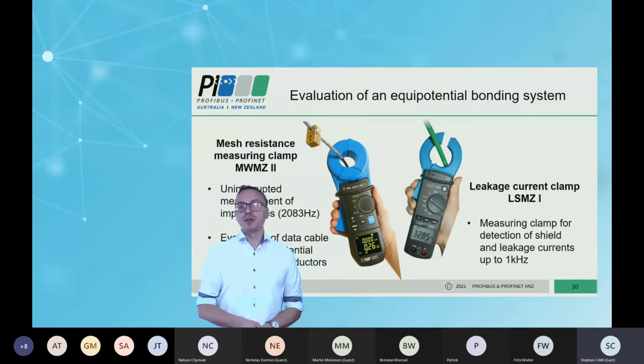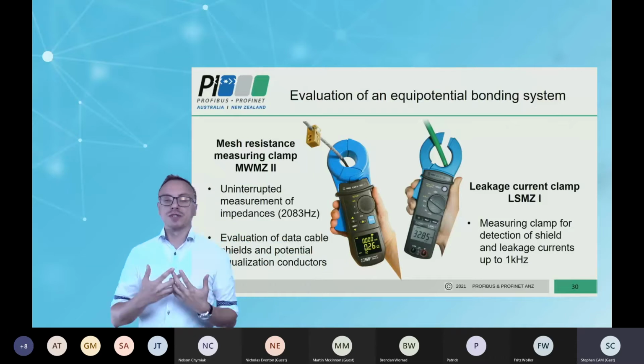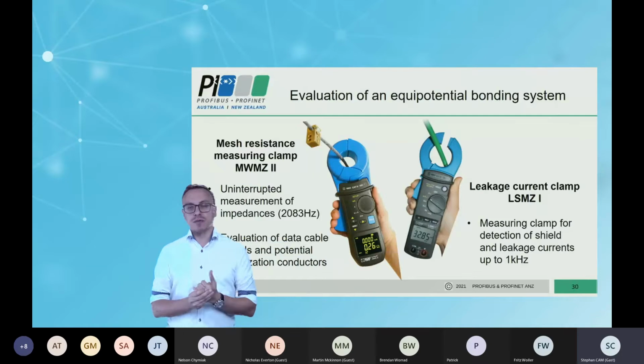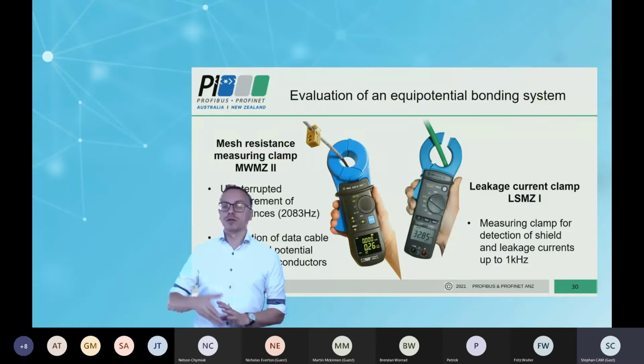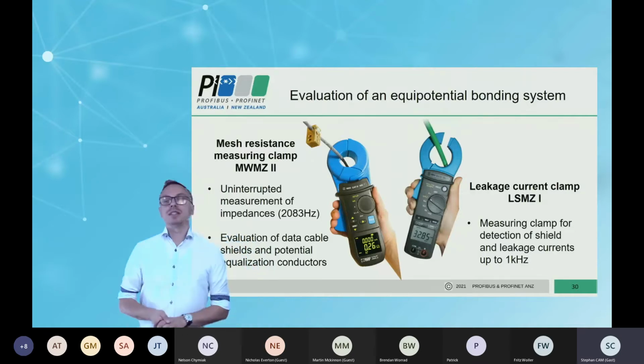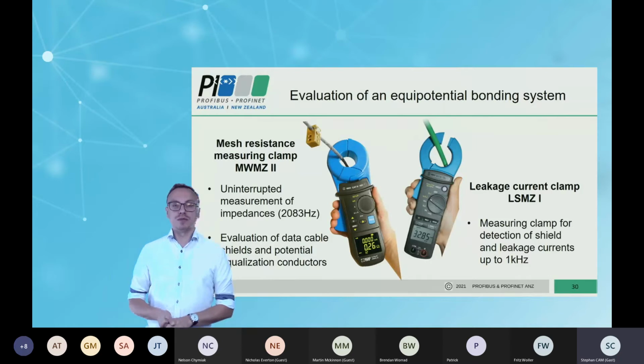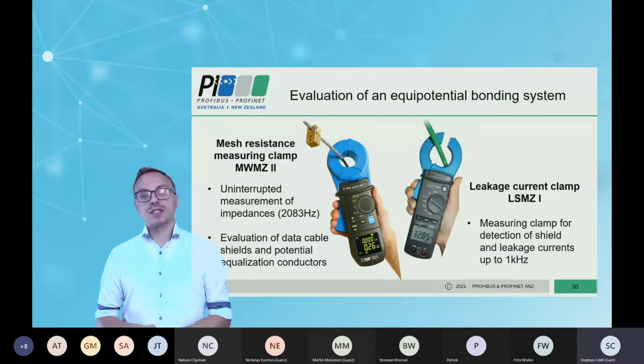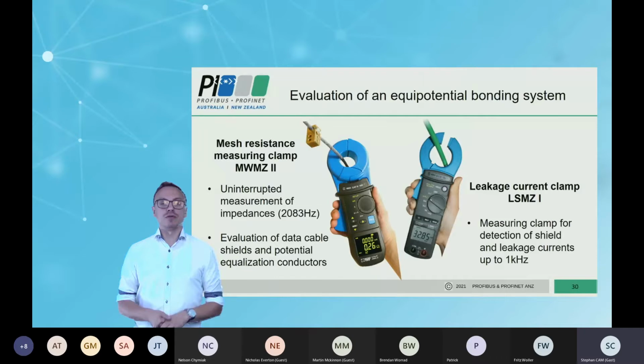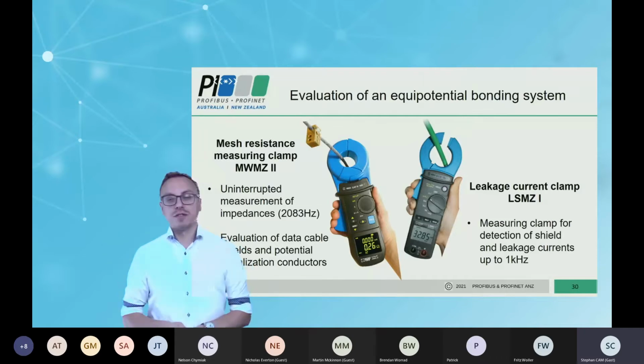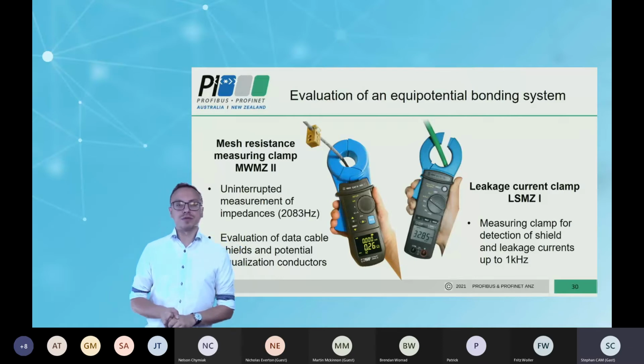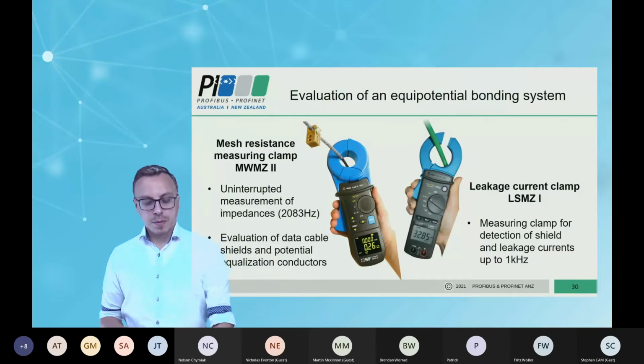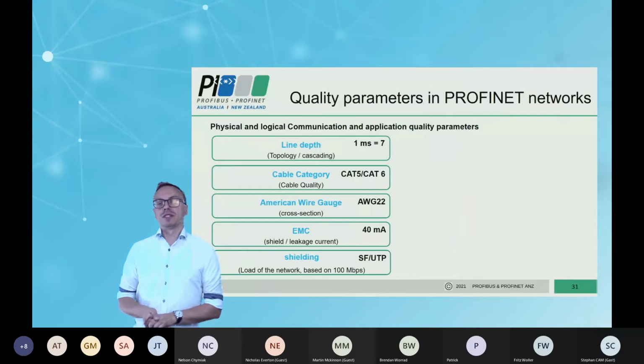Another clamp meter you can find on the market is the normal leakage current clamp, for example, here the LSMZ. With this one, you can measure the current. The recommendation from PI, and also our recommendation, is that you should be around 40 milliamps. If you are over 40 milliamps in new plants, you have to do something. And if you have more than 150 milliamps, you don't have shielding protection anymore. So if you measure your shielded data cable, for example the PROFINET cable, and you measure over 150 milliamps, that means in this situation you don't have shielding protection anymore. It's possible that you get problems because of interference in your system.